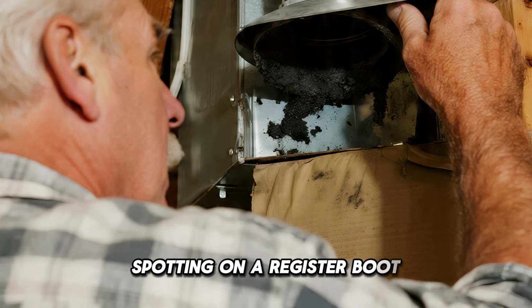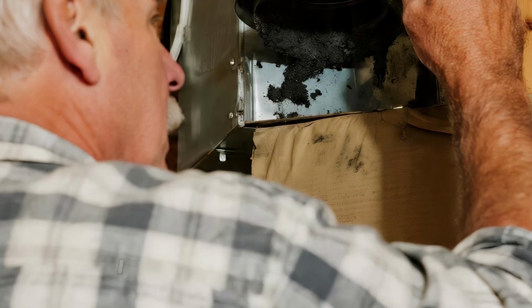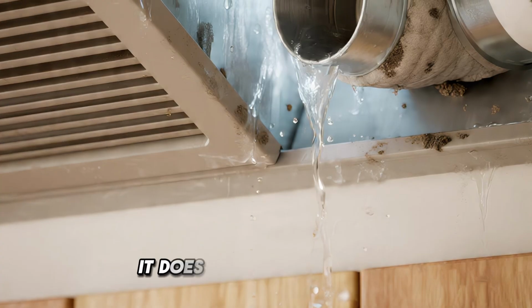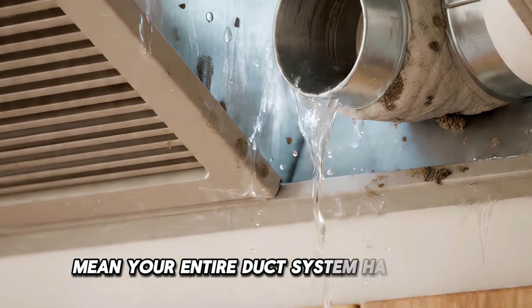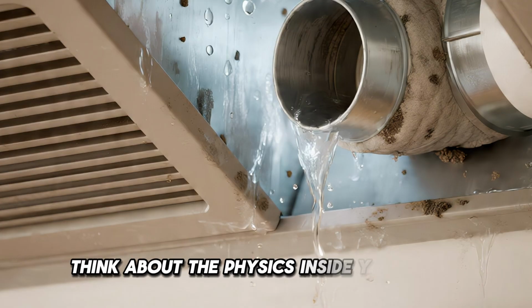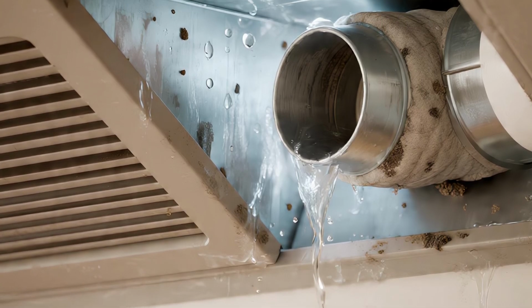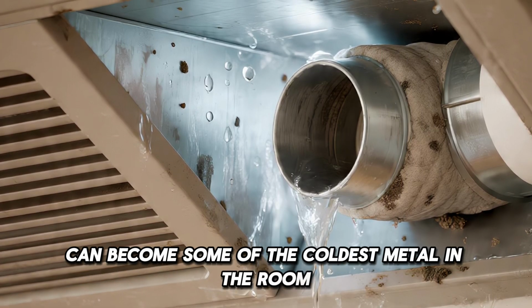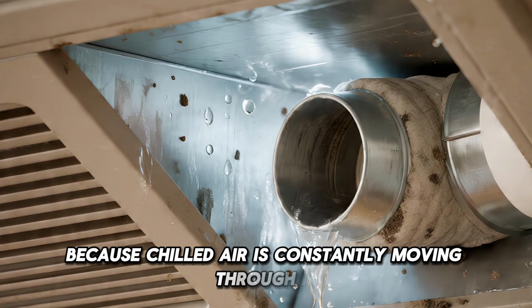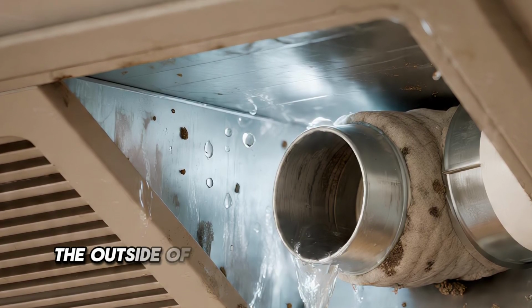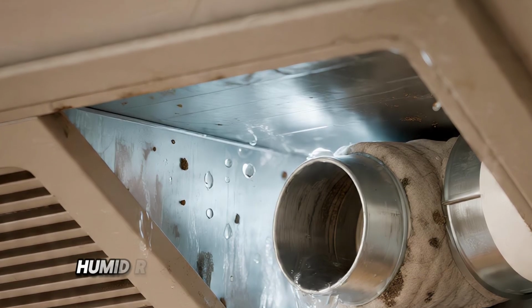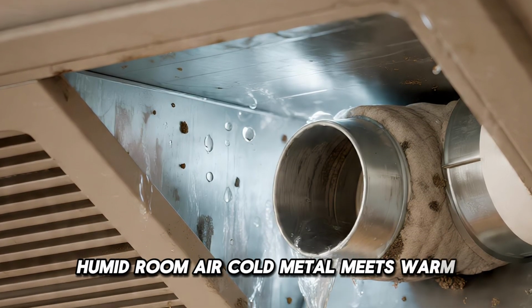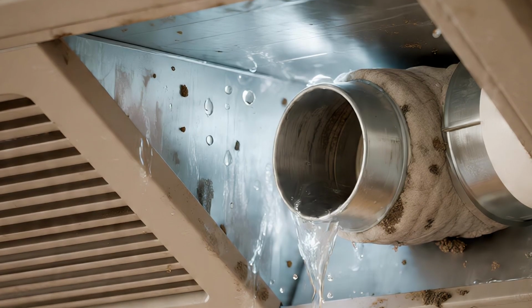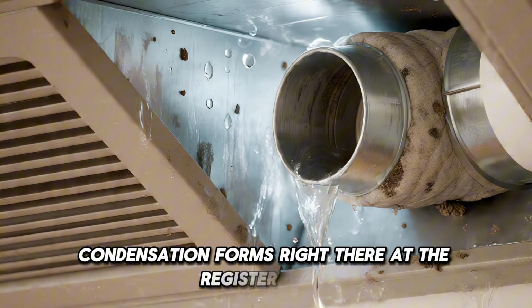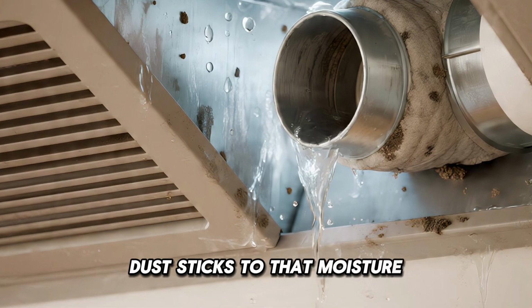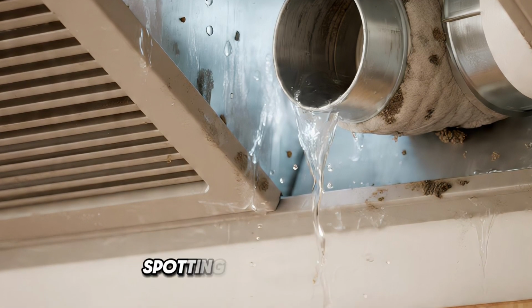Spotting on a register boot that you can literally reach with your own hand is a localized surface problem. It does not automatically mean your entire duct system has failed. Think about the physics inside your home. That metal register boot can become some of the coldest metal in the room because chilled air is constantly moving through it. At the same time, the outside of that metal sits right next to warm, humid room air. Cold metal meets warm, moist air. The metal sweats. Condensation forms right there at the register boot. Dust sticks to that moisture, the area stays dark, and black spotting begins to appear.